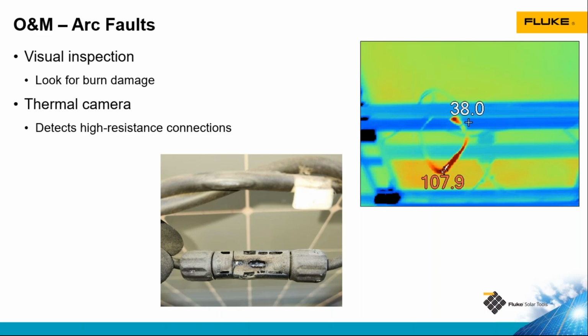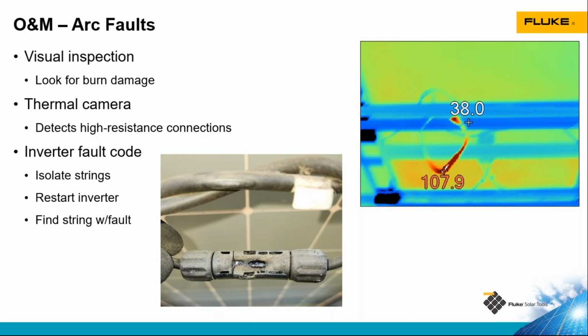Thermal cameras can often find arc faults in connectors. If the arc is bad enough that it's giving off heat, you can find connectors where the temperature is different than other connectors in the system. All inverters these days have arc fault detection built into them. If there's an arc fault in the system, they'll give an arc fault code and the inverter will shut down.